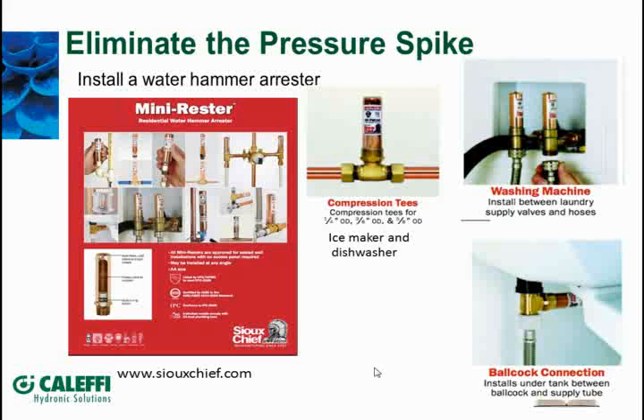I'm thinking, but now you've got 4 check valves in a row, because you've got one in your autofill, 2 in the backflow, and now you just put a 4th one in there. It shouldn't take that many check valves to do a simple protection. So that's one little tip that I'll give you there.